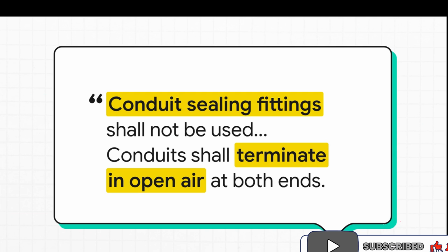Now this quote here points to one of the most critical safety concepts in the whole standard. You know those sealing fittings people use to stop gas from traveling through a conduit? Well, in hazardous areas, you don't use them. Instead, the entire conduit has to run clean through the hazardous zone and pop out into open air on both sides. This simple design trick makes it impossible for dangerous gas to get trapped in your electrical system.